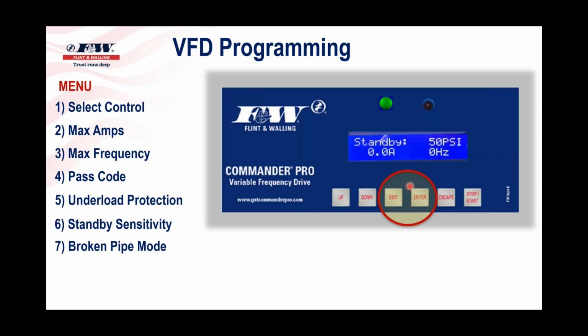But again, this was a nuisance because that pump was not shutting off when we were at sub-zero, and wind chill probably took it down to another 20, 30 degrees below zero. So all we did, folks, is we went into the broken pipe mode and we turned it off. And that problem went away. So there are times you're going to have to come back, maybe hit the edit enter button. But we turned it off. This is an exception to the rule. I told him when spring comes, you might want to put it back on because it's good insurance to have, but just to keep that from nuisance tripping.